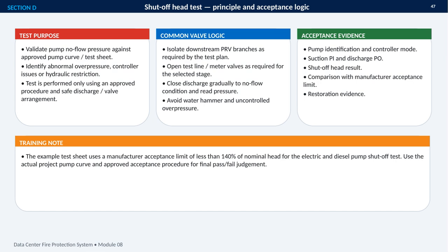The valve sequence is equally important. Downstream pressure-reducing valve branches may need to be isolated, and test line or meter valves are opened according to the selected test stage. The discharge is then closed gradually until the pump reaches a no-flow condition. This must be controlled carefully to avoid water hammer and uncontrolled overpressure.